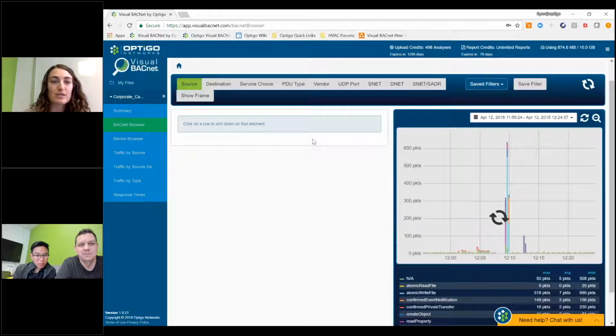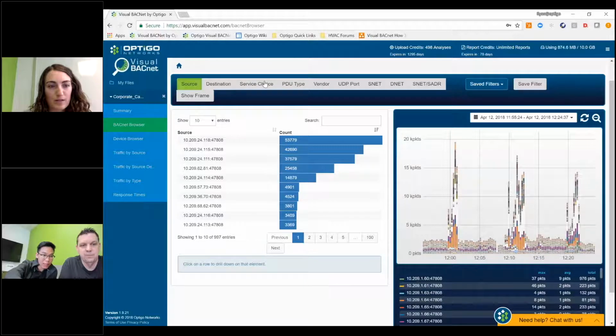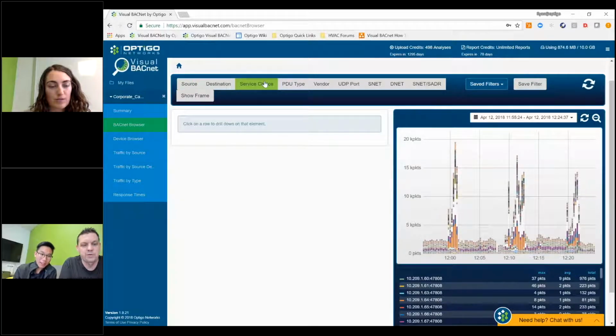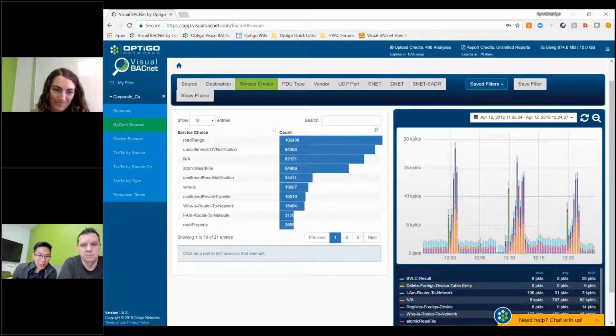If you guys have any questions as we're working our way through this, please ask. Do you want to go to this one? Yep, first one, and then this one first. Okay. So with this, we can see which service choice was the one that's most used. So we can still see this. So every 12 o'clock, 12:10, 12:20, the same thing, and it's doing all of this information. Ton of read range. Most of it's read range. So on a periodic basis, every 10 minutes, it's doing a massive go out and get read range.